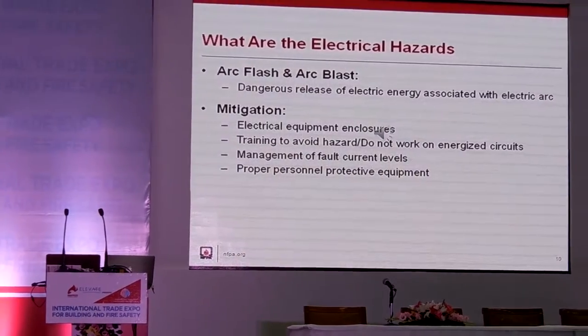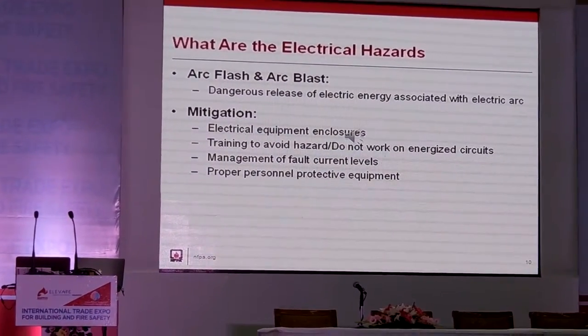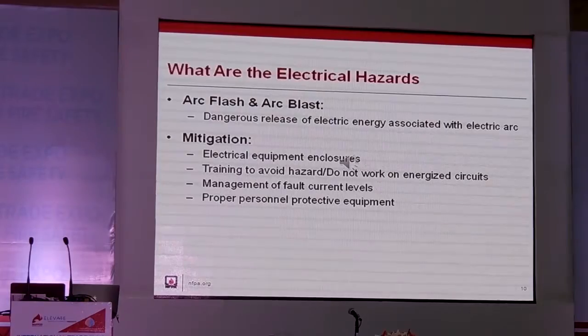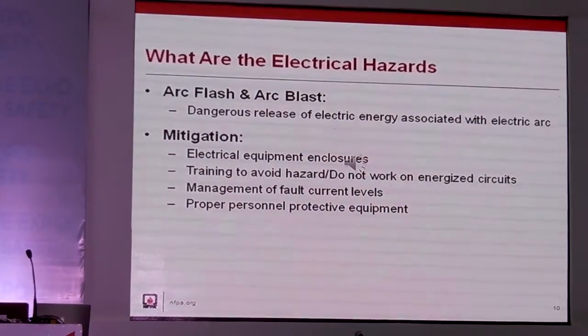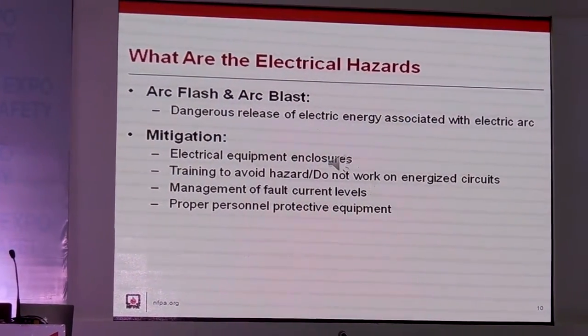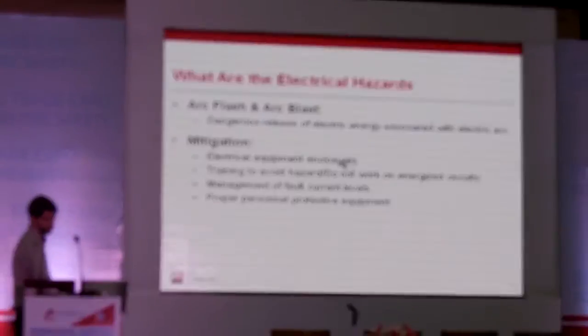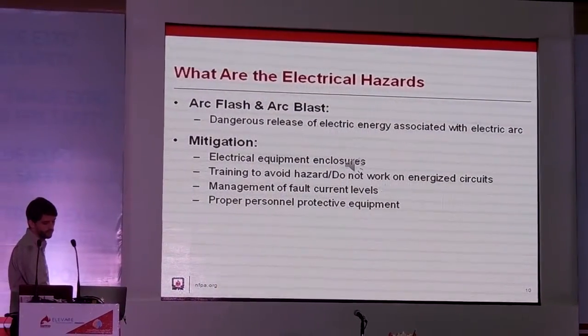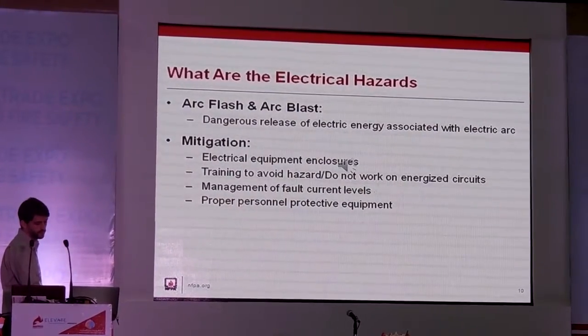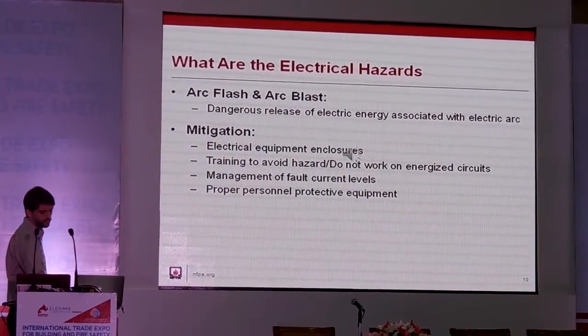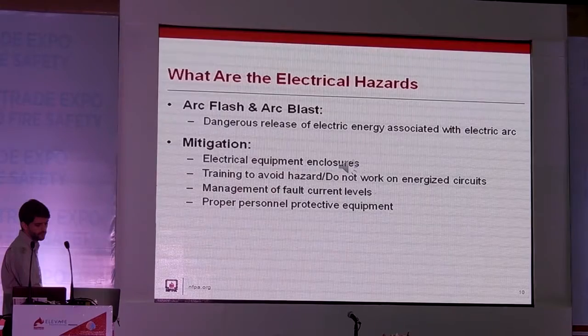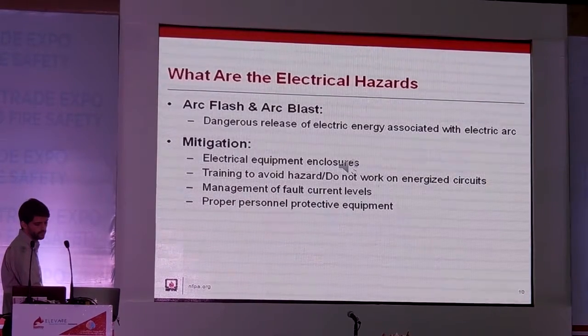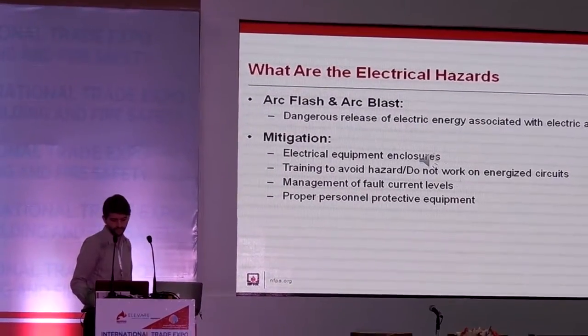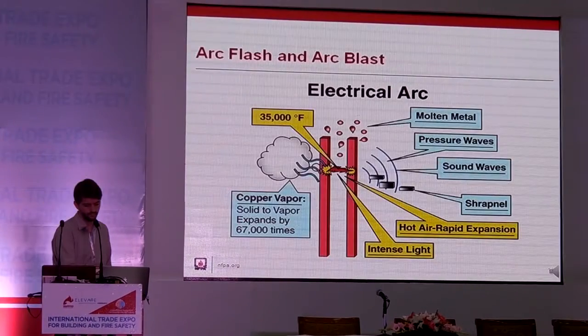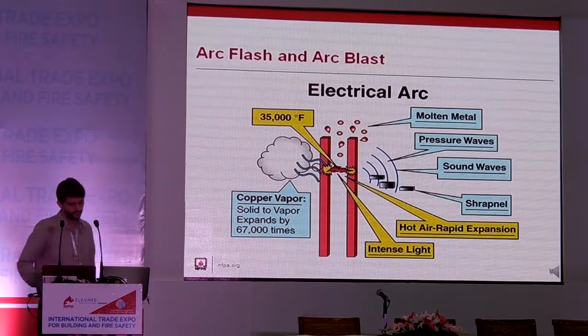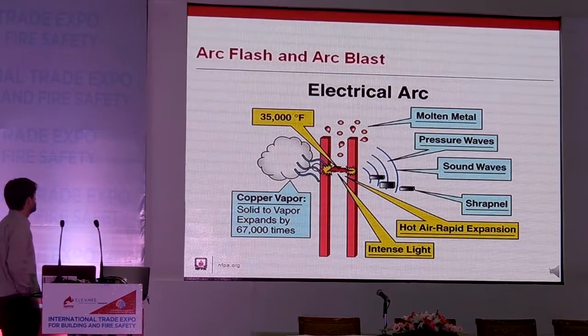Management of fault current levels through the use of overcurrent protective schemes can help reduce the magnitude of an arc flash and arc blast type of event. And then proper personal protective equipment for those workers who do have to work on energized equipment can provide safety if something goes wrong. Tremendous forces are released during an uncontrolled electrical arc.